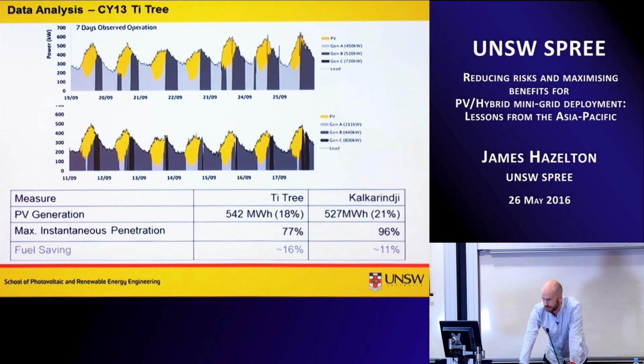In terms of the results, this is an annualised energy contribution of 18% from PV generation. The maximum PV penetration was recorded at 77%, and 96% at Kalkarindji. This is based on 10-minute instantaneous samples, so these figures aren't probably as accurate as they would be if we had bigger data sets, but that's one of the problems. At Kalkarindji, the fuel saving was a little bit lower due to the fact they had one of their generators out and were running a large generator at lower capacity for a lot of the time.